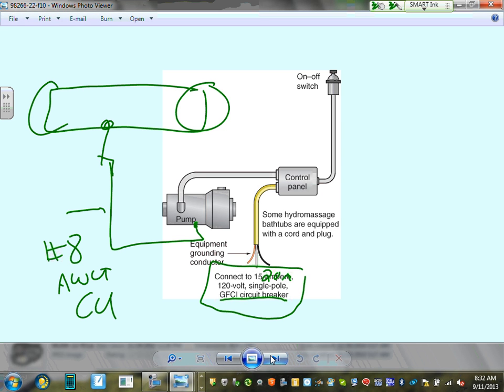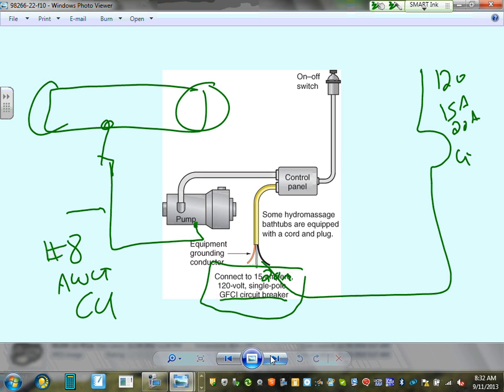Instead of having a GFCI breaker, they put a GFCI receptacle. That's another option. But they don't put the GFCI receptacle right there, it's the circuit breaker. Yeah. So it will be right here, feeding it. That will be 15 amp or 20 amp. Typically, I do them 20 amp, 120 volt, GFCI right here. That's one option.